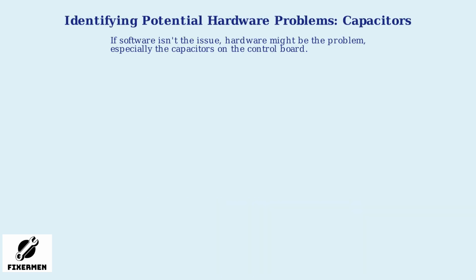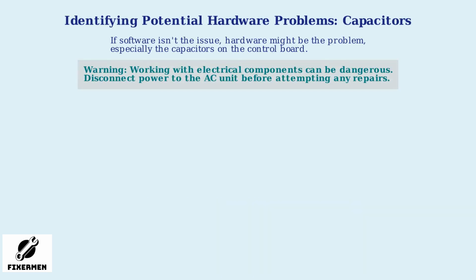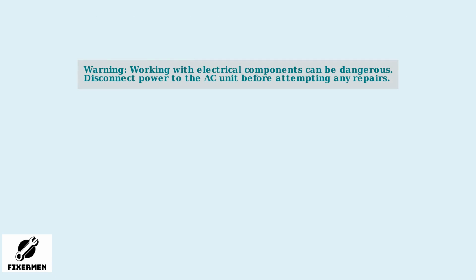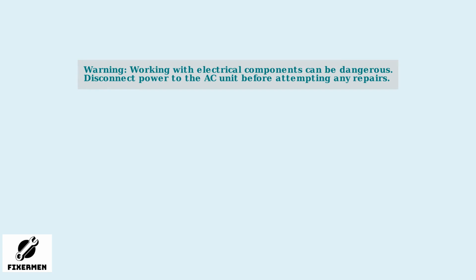If software updates and resets haven't resolved the stuck delay mode, the issue may be with hardware components, particularly the capacitors on the control board. These capacitors store electrical charge and help regulate timing in the AC system. Begin with a visual inspection of the capacitors. After safely disconnecting power, locate the control board capacitors. Check for signs of damage such as bulging tops, leaking electrolyte fluid, or corrosion. These visual indicators suggest the capacitor has failed and needs replacement.